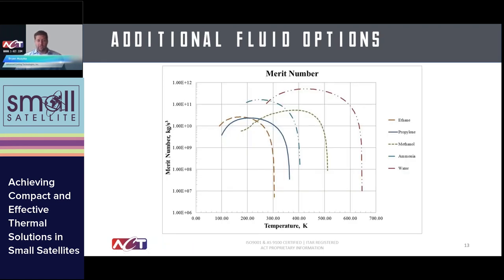Before moving away from heat pipes, there are many different fluid options. We actually manufacture liquid metal heat pipes up to 800°C. In the space realm, the typical fluids include ammonia and water, which we've covered at length. The MERIT number is a well-known heat pipe figure of merit that predicts performance based primarily on fluid properties — water and ammonia are near the peak for their respective temperature ranges. For lower temperature ranges, ethane has been used. Methanol also provides a less capable option than water for component-level cooling if you don't want to worry about freezing, though performance will be lower.